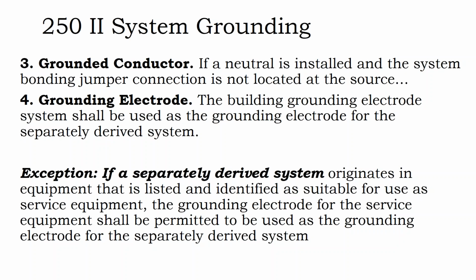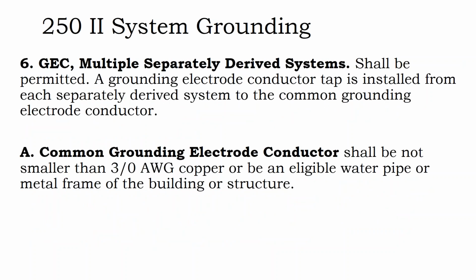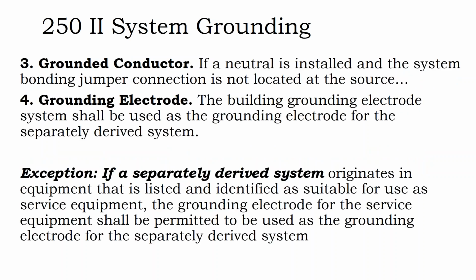You might have two parts of the building that are on completely different electric services, and you may not want to run all the way back to the building's original grounding electrode. It may not be a grid connected system. It may just be running on batteries and a solar array and a generator. So there are exceptions to not connecting everything up together. A common grounding electrode conductor shall not be smaller than 3/0 copper, or an eligible water pipe or the metal framing of a building or structure. So it's common to see 3/0 grounding electrode conductors.